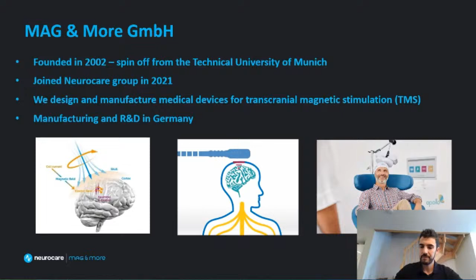The system comprises multiple parts. You have the stimulator, which is able to generate really, really strong magnetic pulses. So it's able to store kilovolt voltages and emit several amperes within microseconds through what we call a magnetic stimulation coil. And this stimulation coil we can then position at different target spots on the head and very focally aim for spots that we want to go for. And then we can emit magnetic pulses.